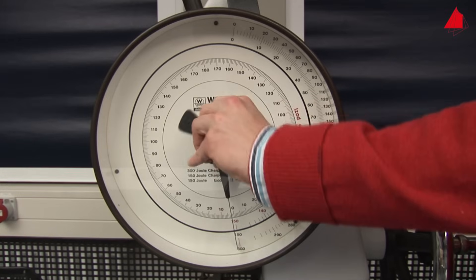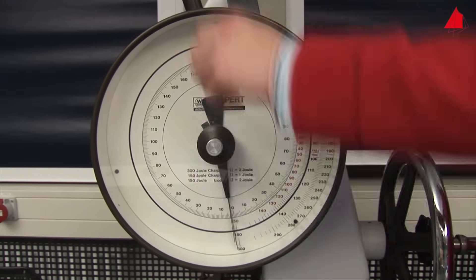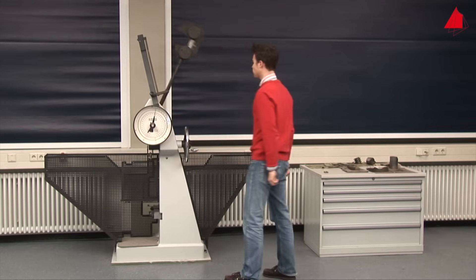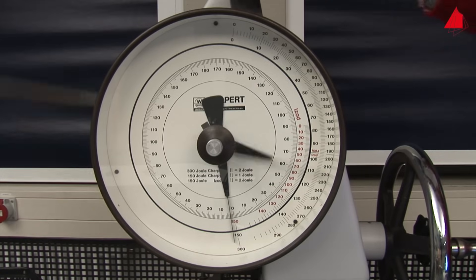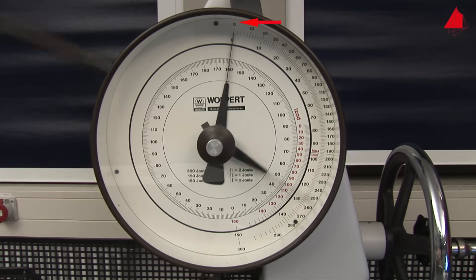In order to do this, he turns the drag indicator downwards and releases the pendulum without a test specimen. The drag indicator stops at position 0. This proves that the pendulum has the correct starting position and that the friction is correctly compensated.